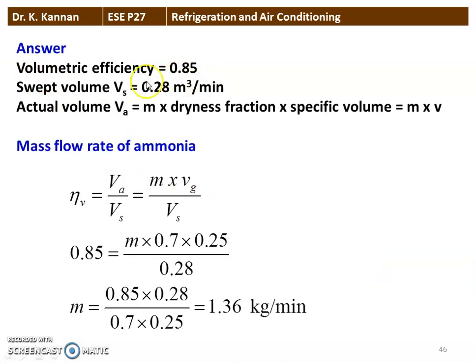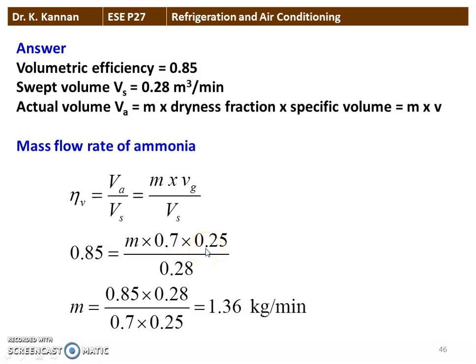The volumetric efficiency of the compressor is 0.85. Swept volume is 0.28 meter cube per minute. Volumetric efficiency equals actual volume divided by swept volume. The actual volume is mass into dryness fraction into specific volume of the ammonia refrigerant — it is wet refrigerant, so X into Vg divided by Vs. Substituting: 0.85 equals mass into X equal to 0.7, into 0.25, divided by 0.28. Rearranging and calculating, M equals 0.85 into 0.28 divided by 0.7 into 0.25, equal to 1.36 kilograms per minute. That is the answer.